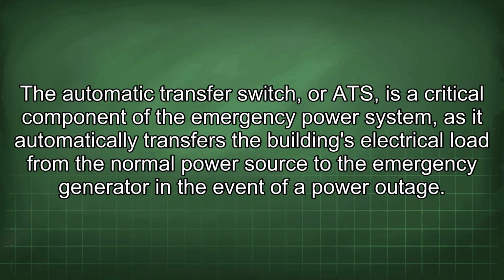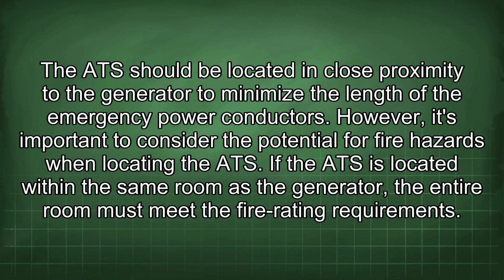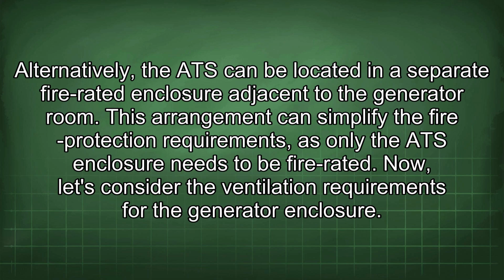of the barrier. The automatic transfer switch, or ATS, is a critical component of the emergency power system, as it automatically transfers the building's electrical load from the normal power source to the emergency generator in the event of a power outage. The ATS should be located in close proximity to the generator to minimize the length of the emergency power conductors. However, it's important to consider the potential for fire hazards when locating the ATS. If the ATS is located within the same room as the generator, the entire room must meet the fire rating requirements. Alternatively, the ATS can be located in a separate fire-rated enclosure adjacent to the generator room. This arrangement can simplify the fire protection requirements, as only the ATS enclosure needs to be fire rated.